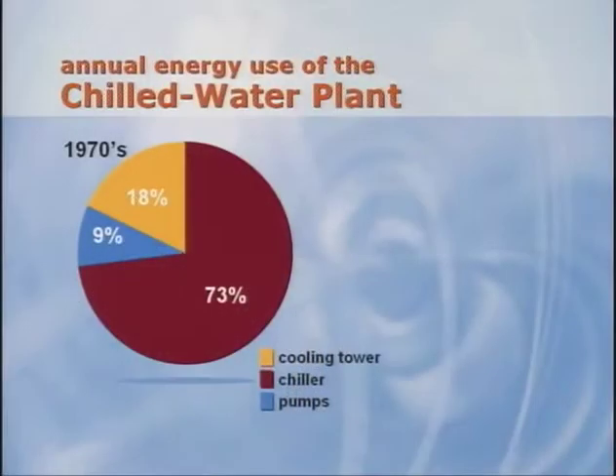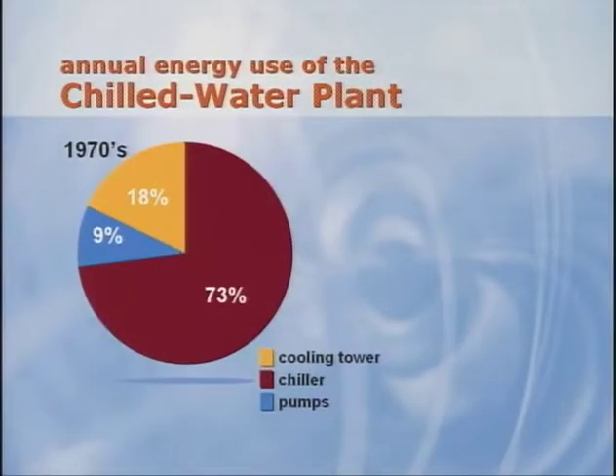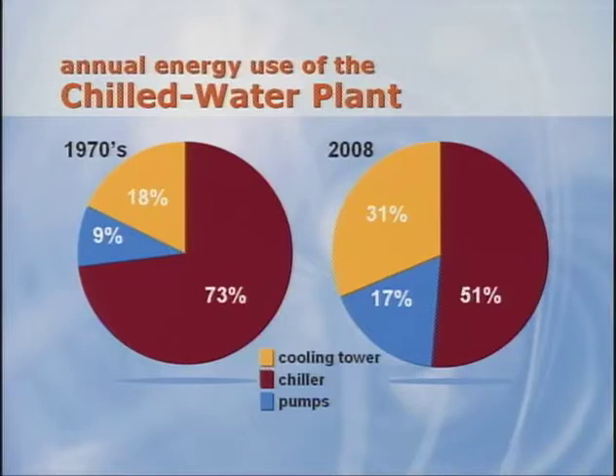Traditionally, the performance of a chilled water system focused on the chiller because it was the largest energy consumer in the plant. 30 years ago, the chiller accounted for about 70% of the annual energy used by the chiller plant, while the pumps and cooling towers accounted for the remaining 30%. However, manufacturers of chillers have made and continue to make great progress in improving chiller efficiency. So much so that today pumps and cooling towers make up nearly half of the plant's annual energy use. So while using a high-efficiency chiller still has a significant impact, this shift has created more opportunities to reduce overall plant energy use by examining the interaction between pumps, towers, and chillers.